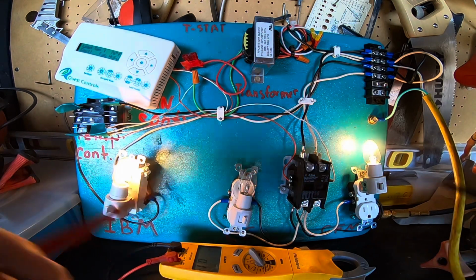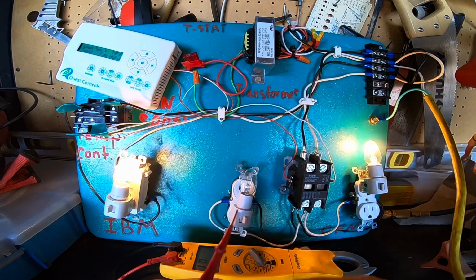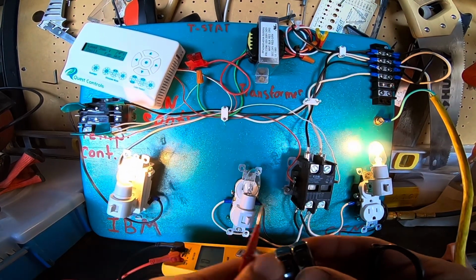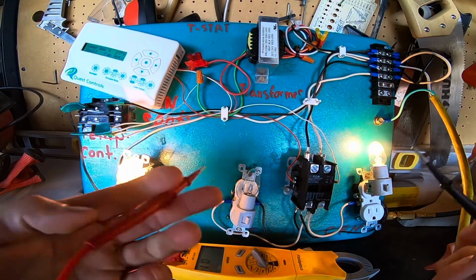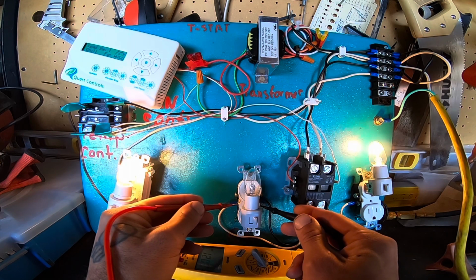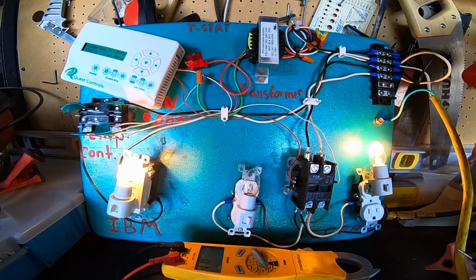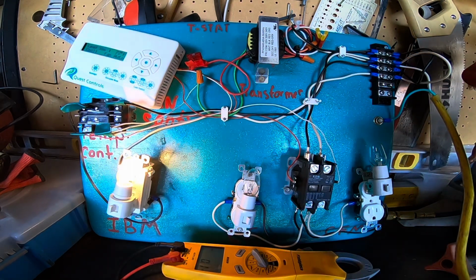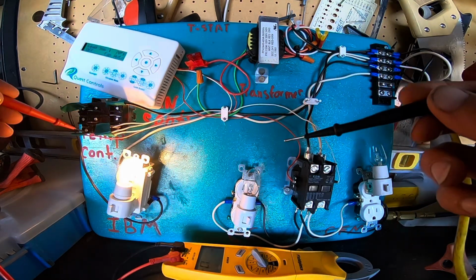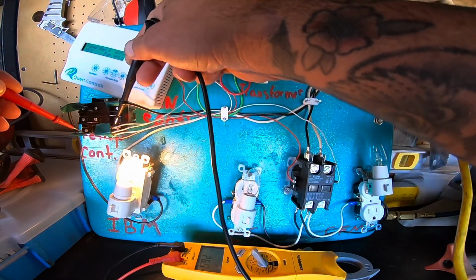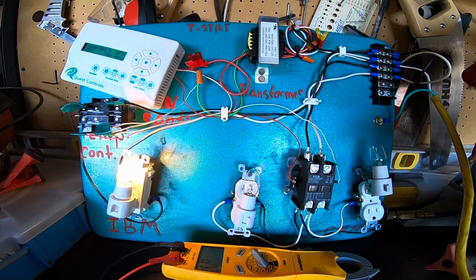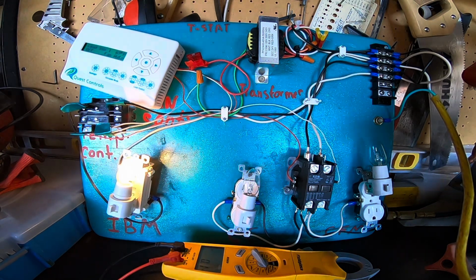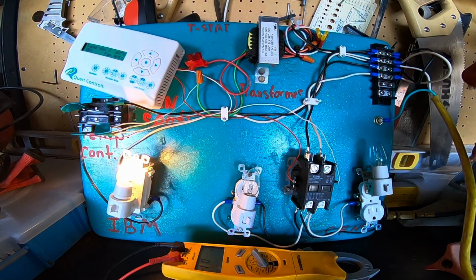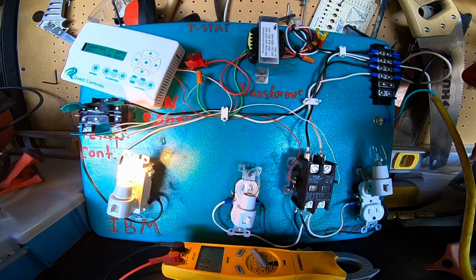So you always want to check power at the winding. You want to check the power that's being supplied. You have the positive and negative. You have the black wire and the white wire. You just check between the two. Oh, look, I have power to the motor and it's not working. So obviously the motor's bad. Obviously troubleshooting the capacitor. And then cool, our call for cool shut off. Let's make sure that the fan is still calling. Yep, it still has 24 volts. So what helped me in the industry was just properly troubleshooting the windings and then having a good understanding of how they're energized.